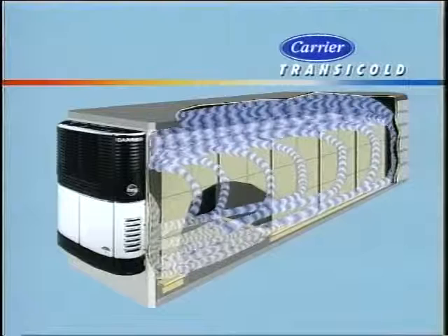The up and down arrow keys are used primarily to change set point and to scroll through information lists we'll be looking at later on in this program. The equal key will be used to enter new set points, start a pre-trip test, set a trip start, as well as other functions we'll also discuss later. The manual defrost key allows us to place the unit into a defrost cycle manually. The alarm list key is used to look at any alarms that may be present.